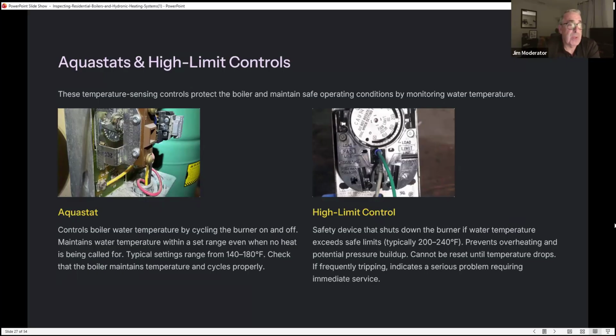Aquastats and high limit controls. These temperature sensing controls protect the boiler and maintain safe operating conditions by monitoring water temperature. An aquastat controls boiler temperature by cycling the burner on and off, maintains water temperature within a set range even when no heat is being called for. Typical settings range from 140 to 180 degrees. Check that the boiler maintains temperatures and cycles properly.